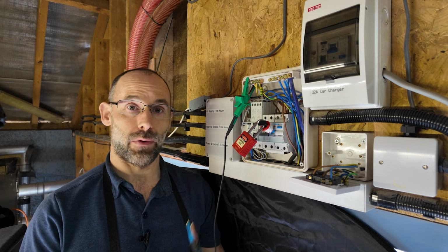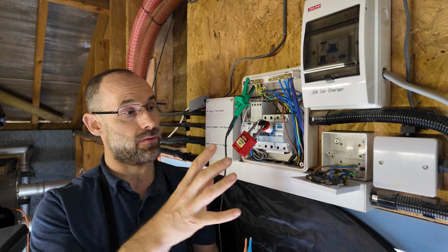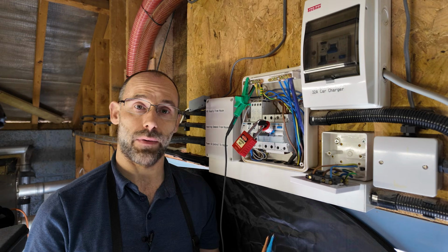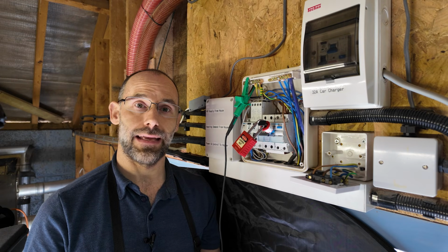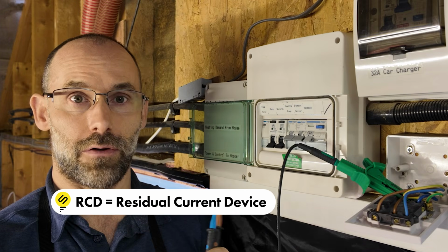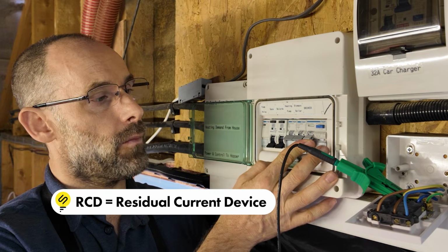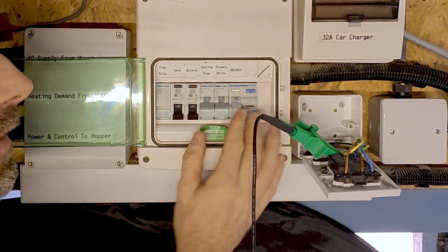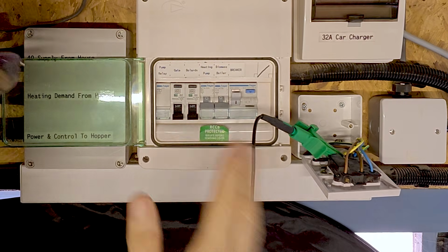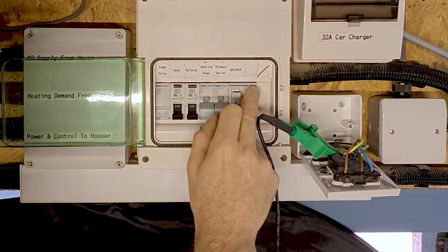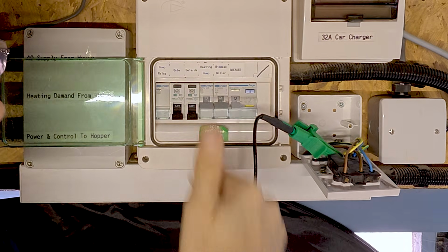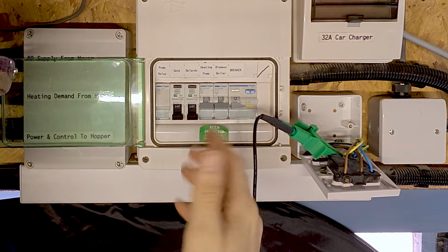That's all good. Now we've finished the live testing, we can put the board cover back on, close all this up, and do the rest of our testing in a safer way. All right, now we want to test the GFCI or residual current device. One way to do that, and you should do this every 6 months to a year, is to be prepared for the ensuing power cut and just hit the test button. Dunk. You hear the dunk, it puts a fault current in, turns off, all good.